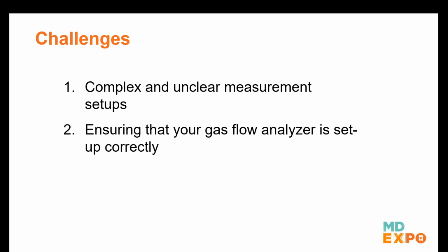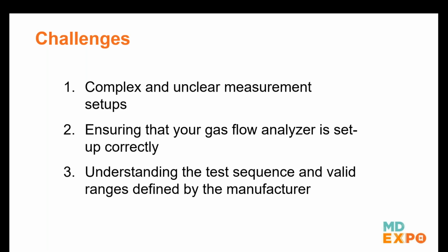Ensuring that your gas flow analyzer is set up correctly. There's a lot of settings on your analyzer. We're going to talk about some of those and help you with those. And we want to make sure that you're understanding the test sequence and the ranges that are defined by the manufacturers. We're going to see that sometimes those are pretty ambiguous.